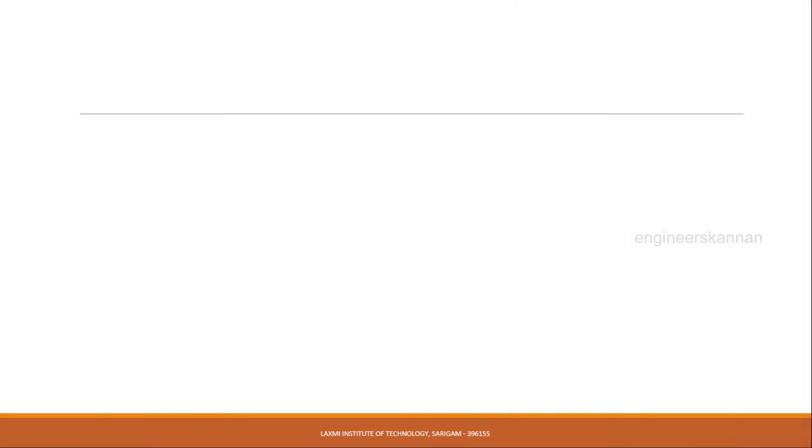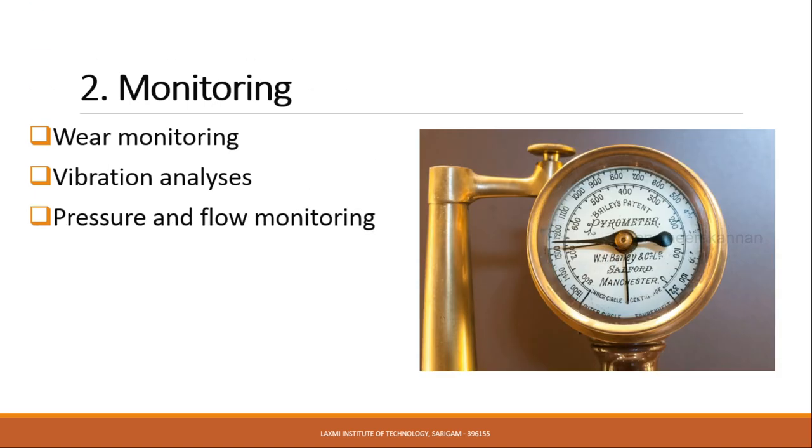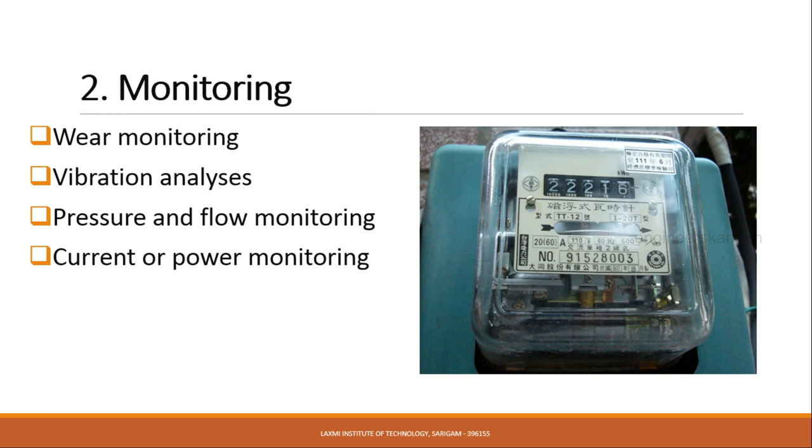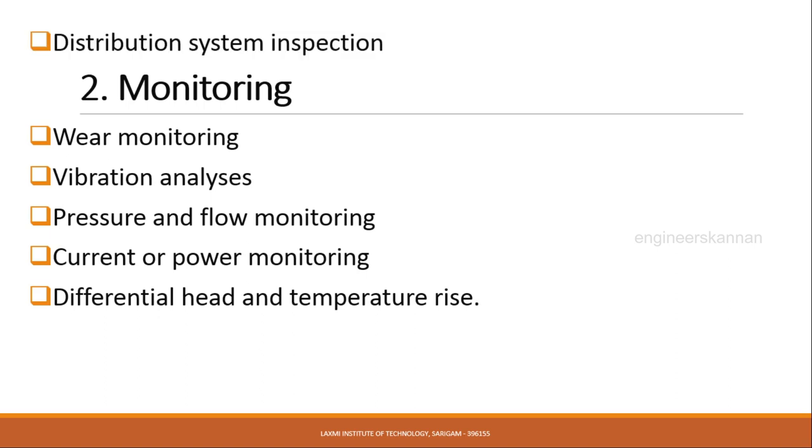The second thing is monitoring. Monitoring in conjunction with operations and maintenance can be used to detect problems and determine solutions to create a more efficient system. This includes bearing monitoring, vibration analysis, pressure and flow monitoring, current or power monitoring, differential head and temperature rise across the pump, and distribution system inspection for scaling or contaminant filter.